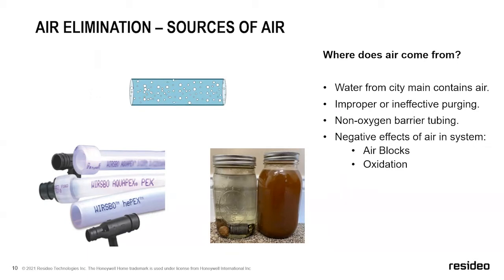The reason I'm going to talk about air elimination is it can be a major problem in hydronic heating systems. Hydronic heating systems are typically closed loop, meaning once you fill it and pressurize it, there's no more water going to be added to this mixture. Once you've isolated that system, filled, purged it, there should be no more water going back in. So as you filled it with this air and water mixture, those air bubbles are going to collect. So a couple things can take place.